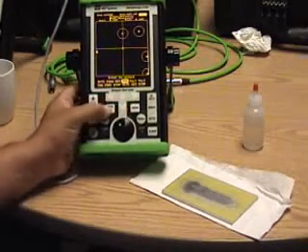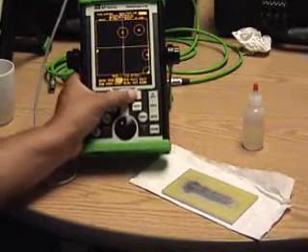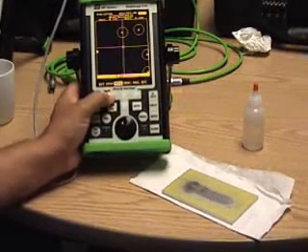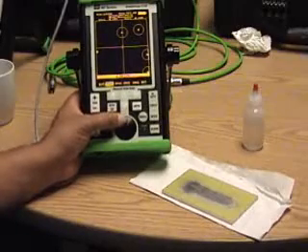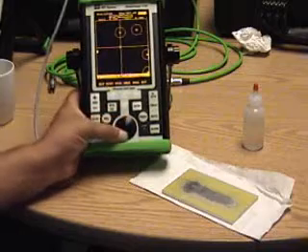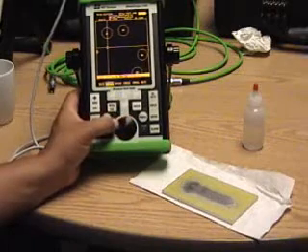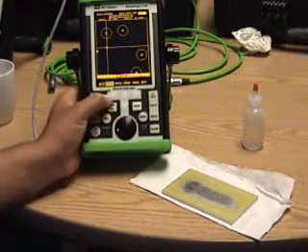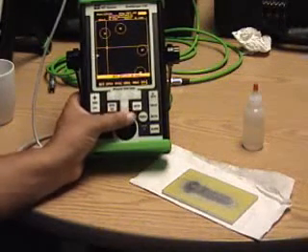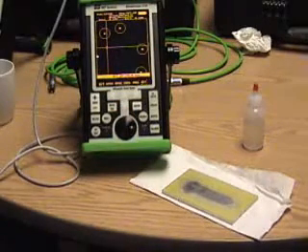By going back to main menu, go to position, press enter, go to X position. It is highlighted. We can adjust it so that we can get more on screen. Now we have all of our dot positions and I can again rotate from this menu also to give us the best separation of all the indications on this particular part.